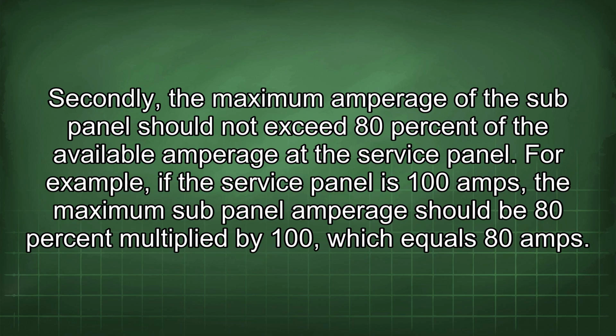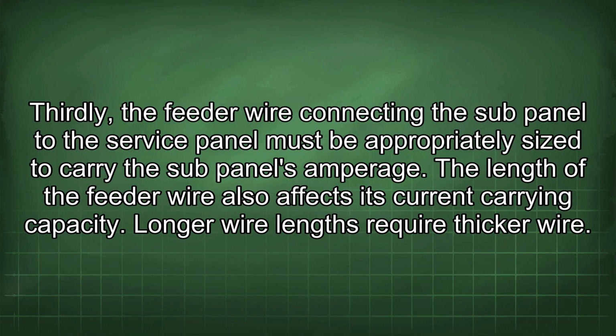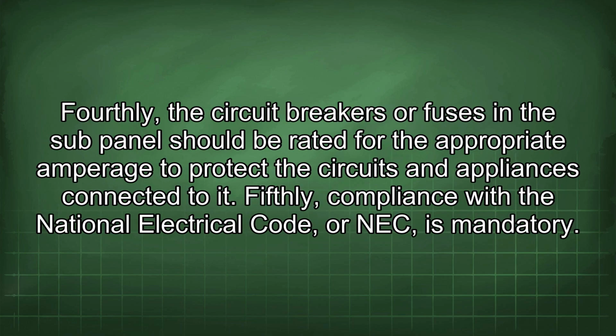equals 80 amps. Thirdly, the feeder wire connecting the sub-panel to the service panel must be appropriately sized to carry the sub-panel's amperage. The length of the feeder wire also affects its current carrying capacity. Longer wire lengths require thicker wire. Fourthly, the circuit breakers or fuses in the sub-panel should be rated for the appropriate amperage to protect the circuits and appliances connected to it.